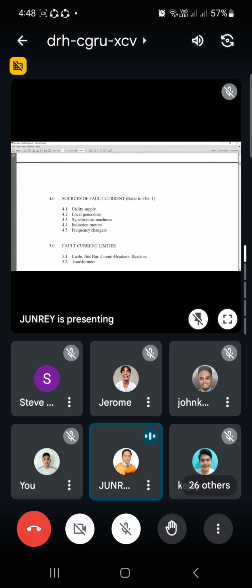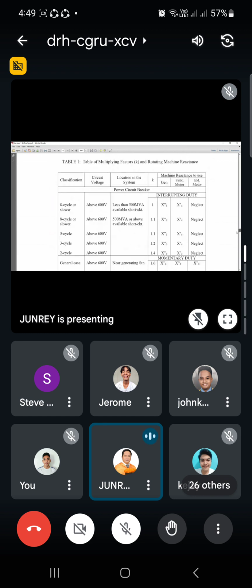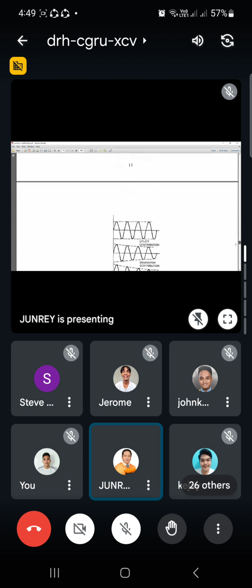So the sources of fault current are, first, the utility supply. The utility supply also contributes fault current. Generators, local generators, also contribute to the fault current. It is not only a certain machine or equipment that contributes fault current. The synchronous machines, induction motors, and frequency changers. So these are sources of the fault current. So if we are going to look at figure 1 here, there it is.